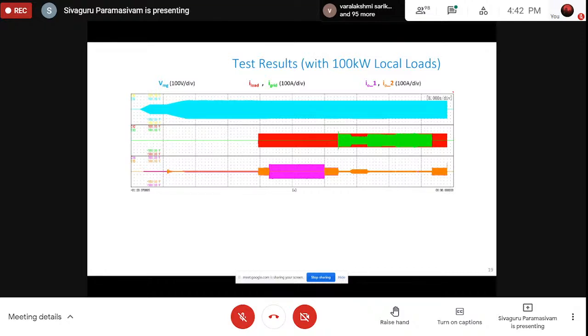So this particular graph is a real life graph made for a 100 kilowatt load testing. You can see that there is a load imposed, which means the load is applied. You can see the graphs here, the current and voltage waveforms at the bottom. You can see whatever happens when the load is applied. And then what we have done is that the virtual synchronous generator inverters are shut down, right? The inverter which was supplying, it's a solar inverter, a renewable inverter. That's shut down. So when the inverters are shut down, you can see the profile changing.